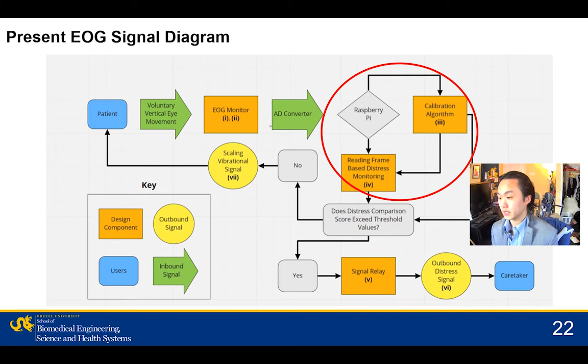Next, we address parameters regarding the device's internal logic system. During calibration, this device will generate expected biases towards frequencies specific to the physiology of the patient due to variability between biosignals of patients. The calibration is very simple and fast on the patient's end. They simply must look straight ahead for 10 seconds and then create a distress signal, vertical oscillations, for 10 seconds. The remaining calculations are all automated.